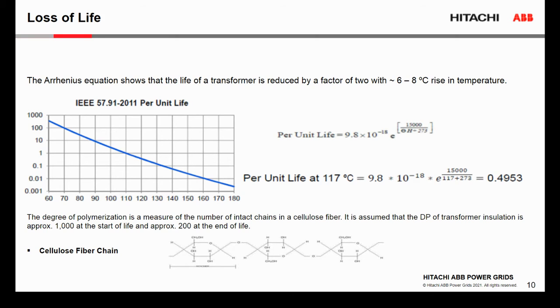And basically, on the conductor, we have paper insulation, and paper insulation has something which is called a polymer chain, and this is the length of the chain in the cellulose fiber. Normally, the new transformer has DP in the range of 1,000. After 30, 40, or 50 years, DP goes down, and at the end of the life, DP is 200 or less, which means that the mechanical strength of paper insulation is much lower, and we may have a problem with the mechanical strength or short circuit strength due to the paper conductor being weak at this point.